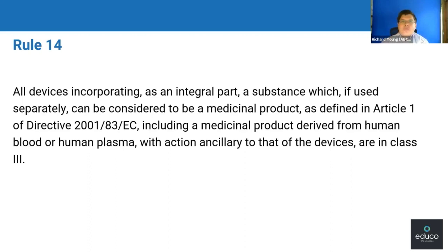And that's things like medical devices that are coated with heparin would come under that. So heparin's been added in there. It's derived from human materials, potentially. It's a pharmaceutically active medicinal product. It's on there to reduce blood clotting. In a medical device, that's not its primary function. So it's an ancillary function to help the medical device work better. But it's still a class 3 as soon as you add these materials in.